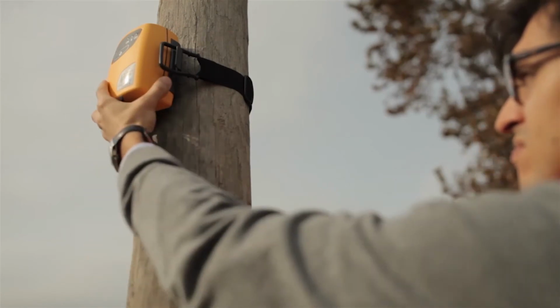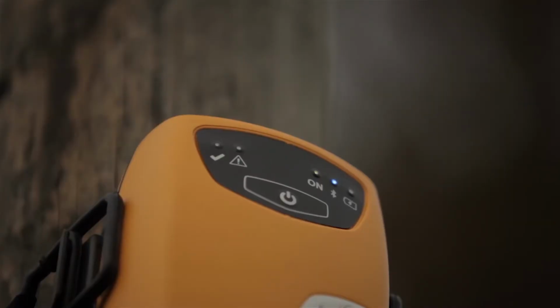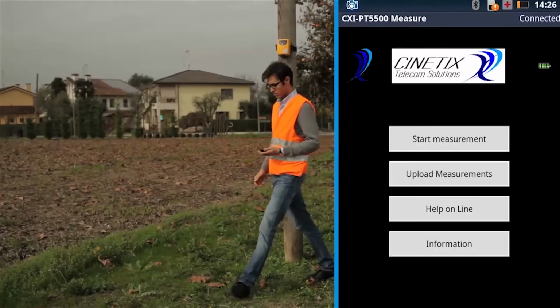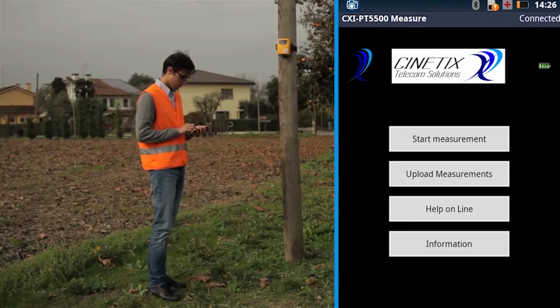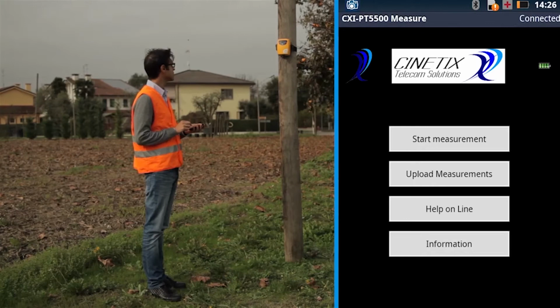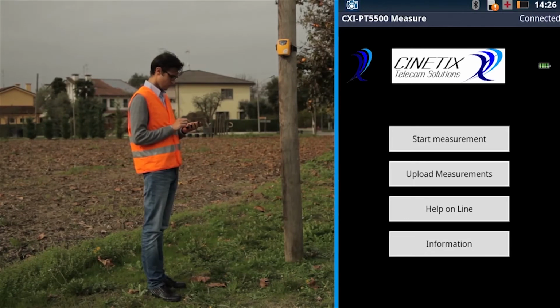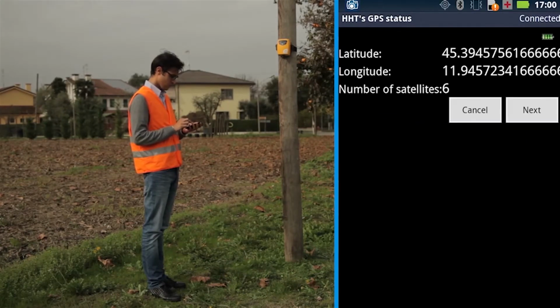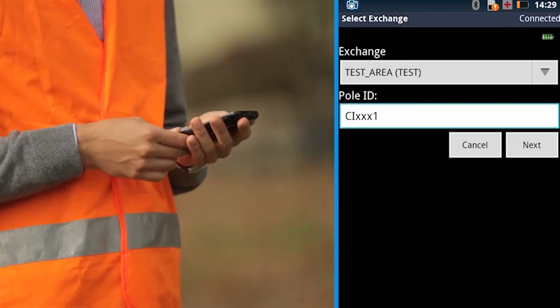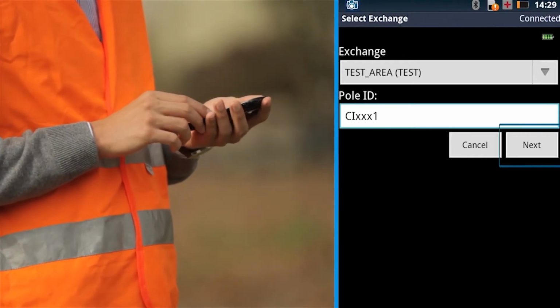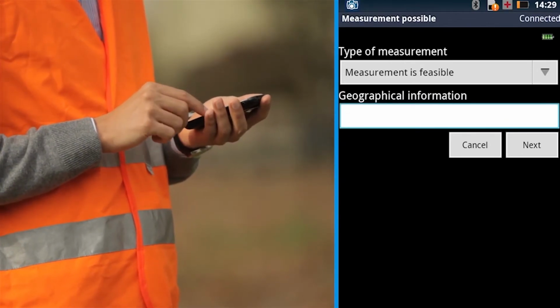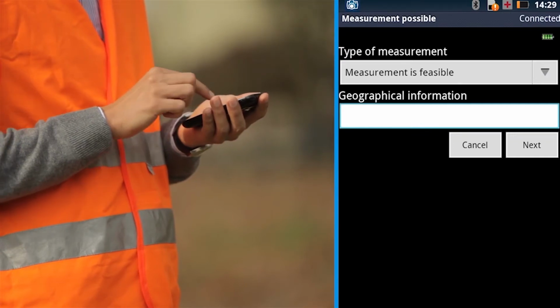Run the CXI PT5500 app in the smartphone and connect the smartphone to the probe. The first phase of the measurement is to enter the pole information. On the main page, press Start Measurements. When the device shows the GPS coordinates, press Next to go on with the measurement. First enter relevant information about the pole, such as its pole ID for future reference.